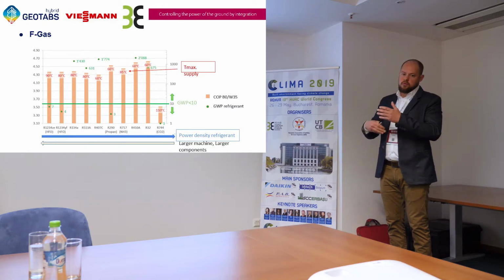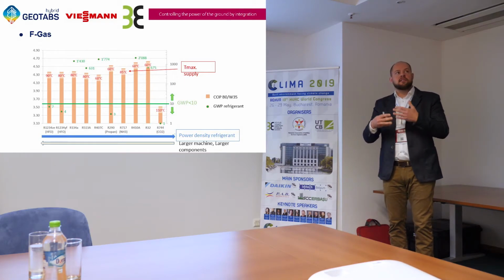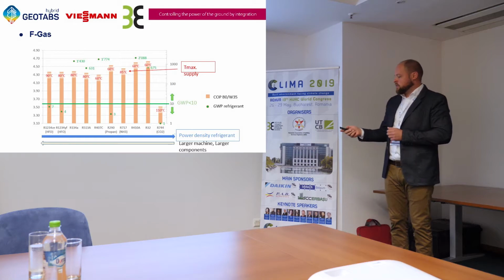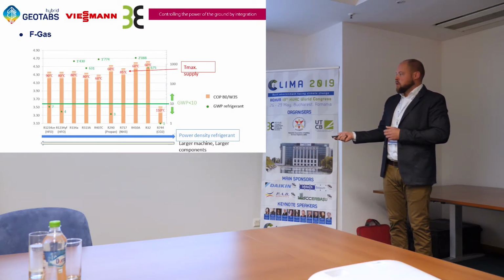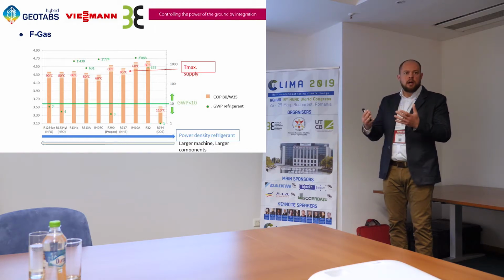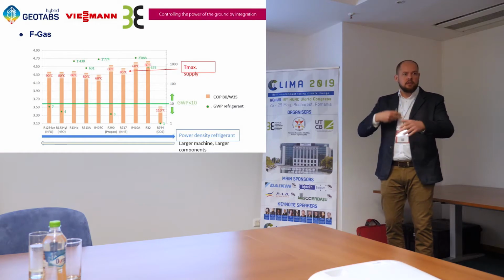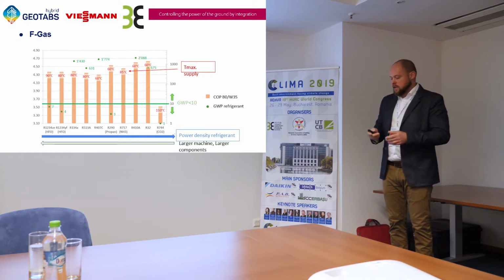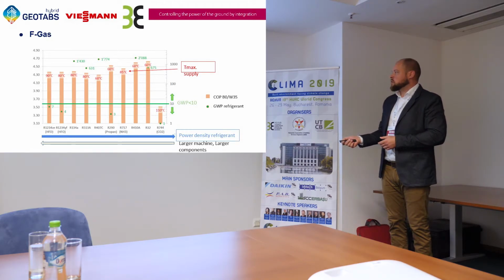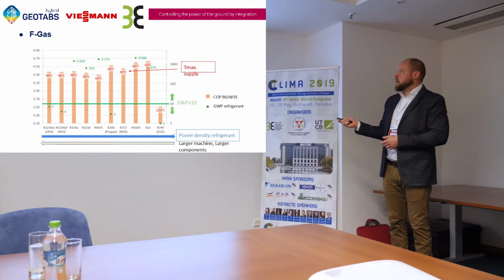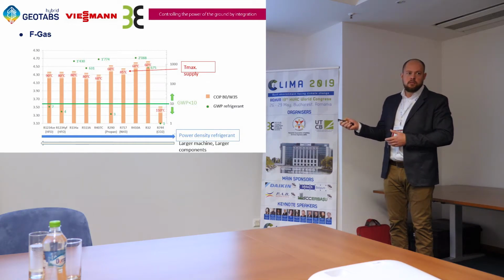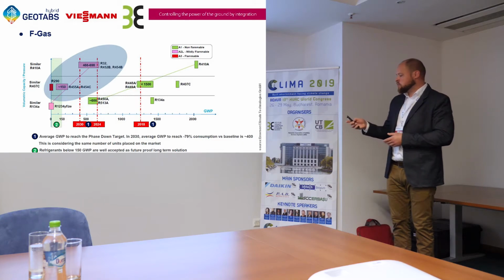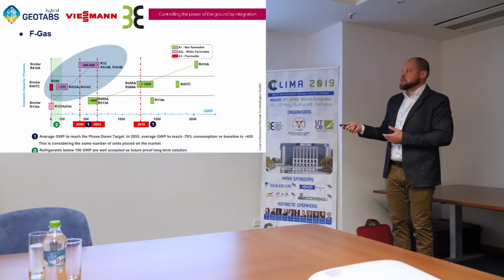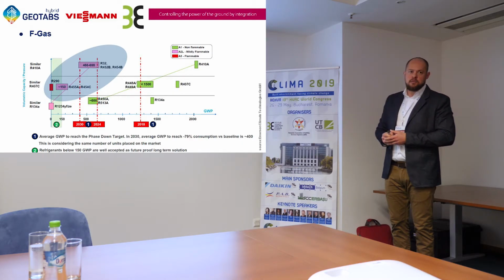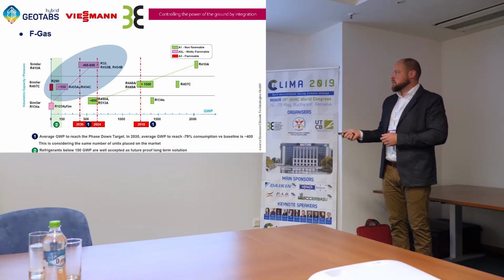So with 410A we have to make less flow of refrigerant for the same power output than, for example, with the newer refrigerants. That means that when we use these types of refrigerants, to get the same power output, we have to use larger components, bigger compressors, to move more refrigerant through the cycle. That's something very important. And also what we saw on the previous slide is the flammability. The green ones are non-flammable. Then the newer refrigerants are mildly flammable, so we have to have special measures in the technical rooms. And propane is highly flammable, so this is often a heat pump that has to be placed outside the building. So that's a bit how we stand today.